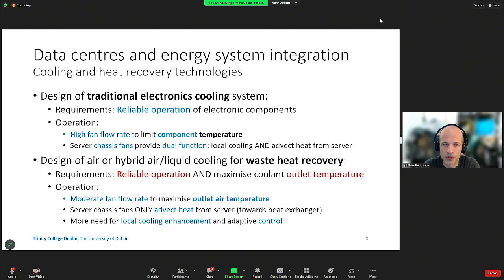So traditionally, electronic systems, like I said, the design goal, the requirement there, was reliable operation. They didn't really care about waste heat recovery. And so that means that the operation typically means that the fan flow rates are generally high. So you want to limit the component temperature and ensure that everything stays cool enough inside. And the chassis fans then in that case provide a dual function. And we'll come back to that later on.